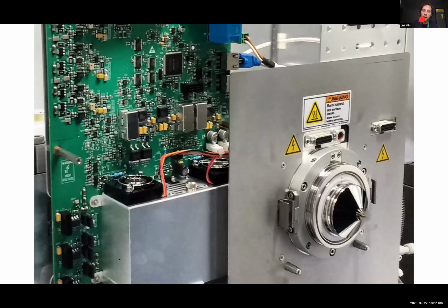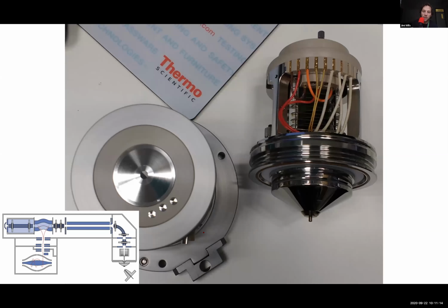So this is where the ions come in, the front of the instrument. This is with the cover off, and you can see stuff behind there. So this is the front of the instrument. This is an ion transfer tube that carries the ions from the outside to the inside, where it's a vacuum on the inside. And because it's a vacuum, the ions try and spread out as they come in, along with the gas and everything else that comes in there.